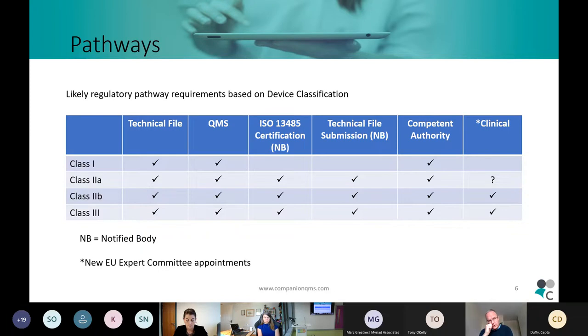If you take the first row, a class one device, which could include something like a surgical face mask that we're unfortunately too familiar with more recently—I worked on a couple of those projects last year—there's an obligation to assemble a technical file and to have a quality management system, albeit not as extensive as for a higher risk device. But there isn't an obligation to have a 13485 certified system certified by a notified body.